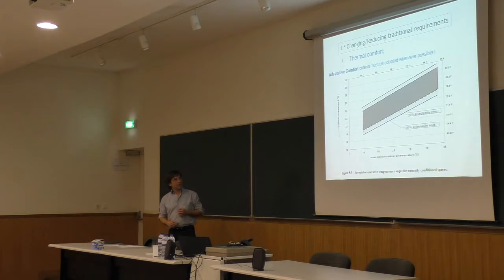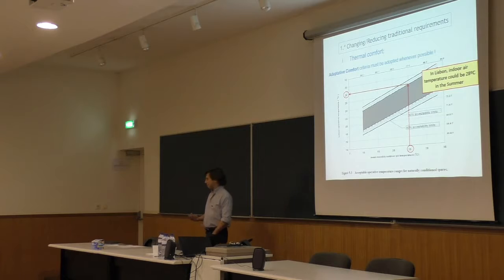For instance, from this standard, we have this chart that shows in the horizontal axis the mean monthly outdoor air temperature, and in the vertical axis, the indoor operative temperature. And this gray area is the area inside which we have over 90% acceptability from the occupants. And this lighter gray is 80%. Okay, let's go to 90. For instance, in Lisbon, we have an average in the summer of 25 degrees Celsius outdoors. At 90%, we could have 28 degrees indoors using adaptive comfort criteria instead of the traditional comfort criteria. Okay?